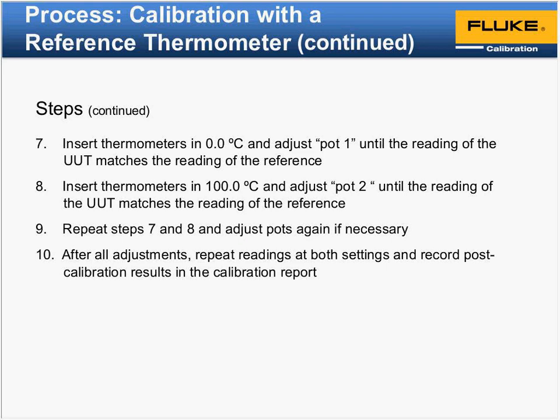All right, the next question is about your sensors. Which ones are the most accurate? So you talked about thermocouples, thermistors, RTDs. Maybe you could just spend a minute on that. Okay, so again, there's a lot out there as far as what you can get for accuracy. And again, most of it is based around range. If you're looking at a fairly small temperature range, 0 to 100 C, a thermistor is probably your best regarding accuracy. Over that temperature range it will net you approximately 0.01 to 0.006 in that sense. From there, you kind of have to go with the trade-offs.